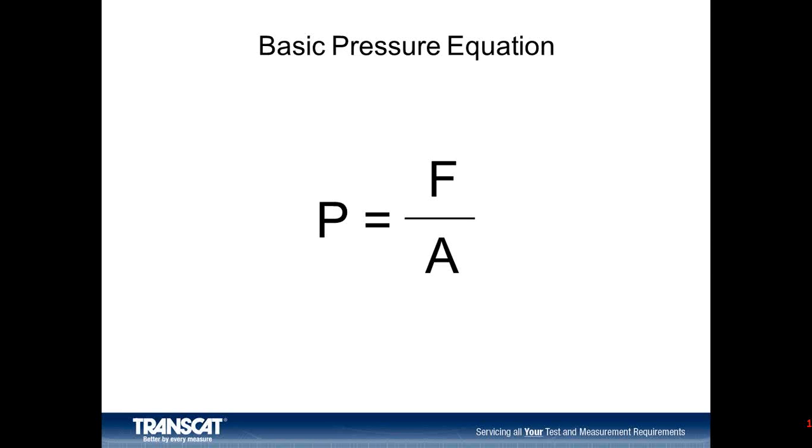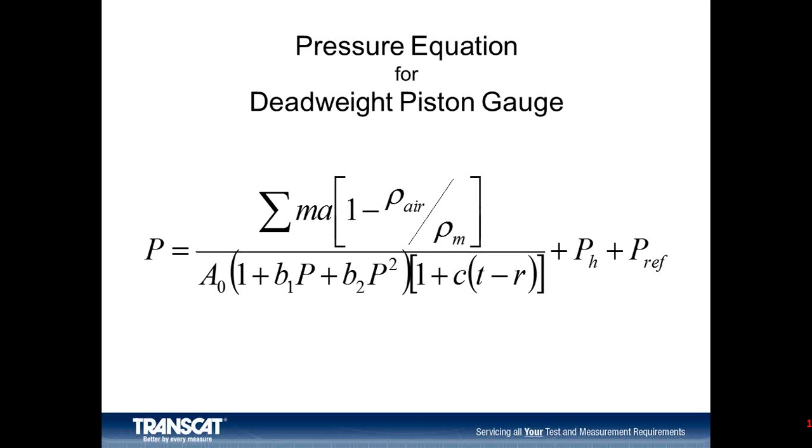So the example I was talking about previously was pressure. The definition of pressure is a fairly simple formula, particularly as it relates to mechanical devices, a deadweight tester, for example, at least on the surface. But when we put it into practice, it evolves into a host of different parameters that have to be accounted for.